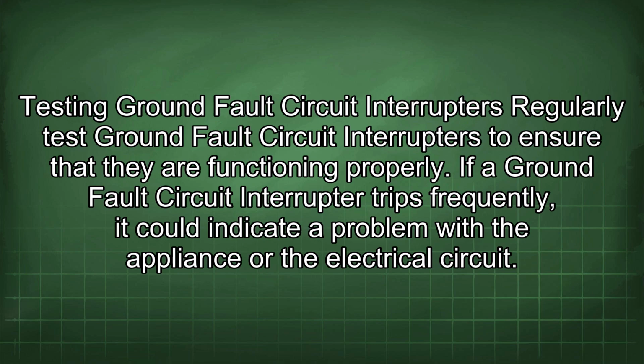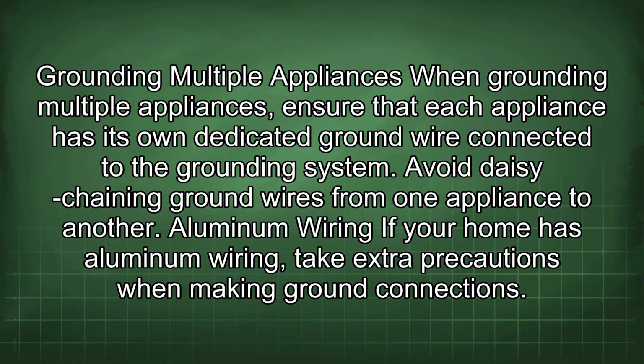Testing ground fault circuit interrupters: regularly test ground fault circuit interrupters to ensure that they are functioning properly. If a ground fault circuit interrupter trips frequently, it could indicate a problem with the appliance or the electrical circuit. Grounding multiple appliances: when grounding multiple appliances, ensure that each appliance has its own dedicated ground wire connected to the grounding system. Avoid daisy chaining ground wires from one appliance to another.